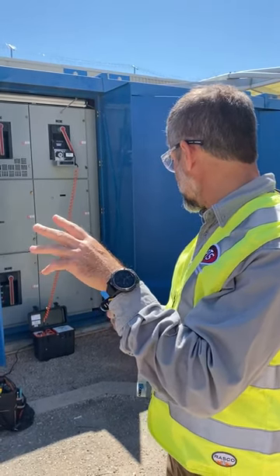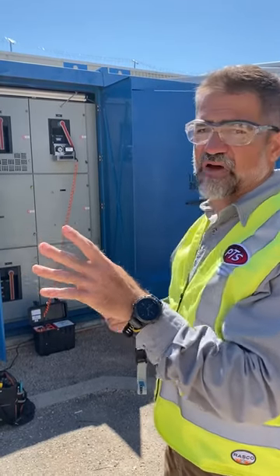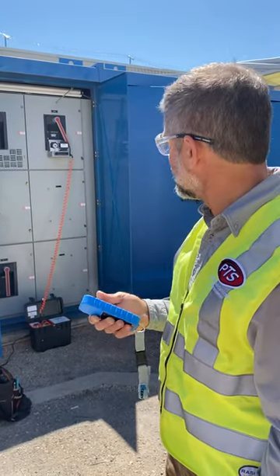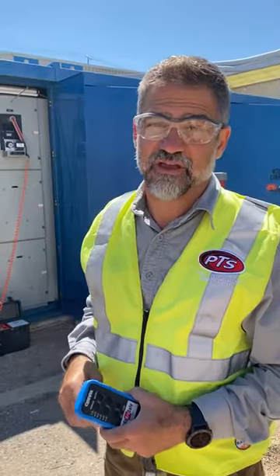It's at one, one and a half, two, four — about five and a half's the peak. And then a few more turns from here, the breaker's racked in. Didn't have to get on the ladder to do that. Totally safe because distance is safety.